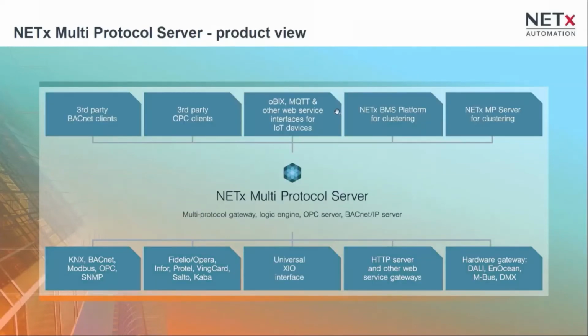This means clustering. I mentioned already previously, besides the BMS platform, we have a second main product, which is the multi-protocol server. And you see easily on the field and automation level, you have available the same drivers, the same interfaces as well. On the management level, you will have the entire communication to third-party applications as well. But what is missing? It does not provide our visualization clients. It does not provide the database and the BMS functionality, because these topics are handled from the third-party SCADA, BACnet or OPC systems or OBIX and MQTT clients as well. So this is an easy to use multi-protocol gateway to connect individual systems easily and provide the data to third-party applications.